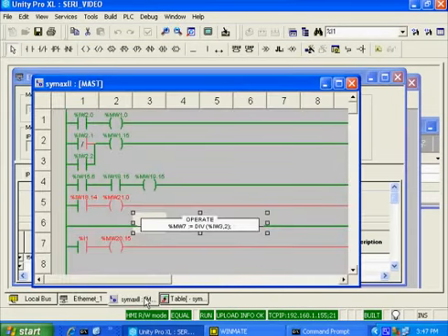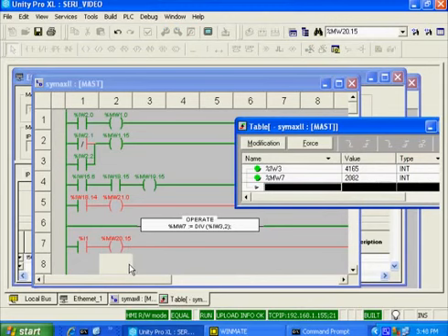The ladder segment looks very much like the Symax ladder. The register numbers are the same, but the bit numbers must be reduced by 1 since Symax bits are numbered 1 to 16, while Unity bits are 0 to 15. The analog values use the operate rung to do the divide by 2 assignment. Rung 7 was added to control a Symax output from the Quantum input.